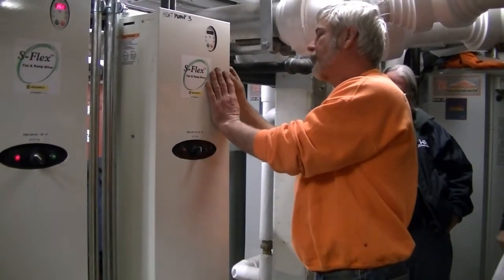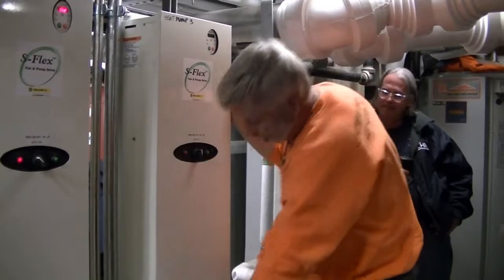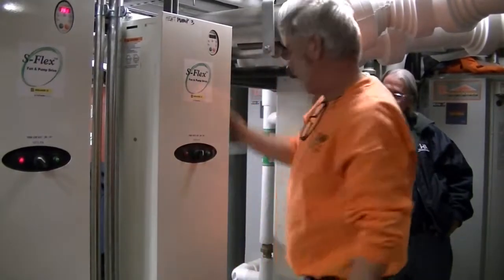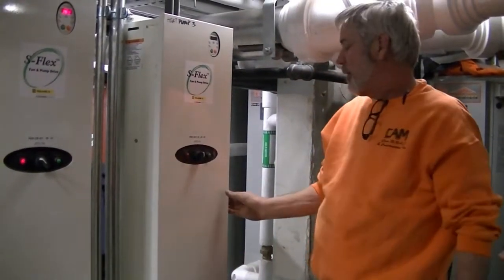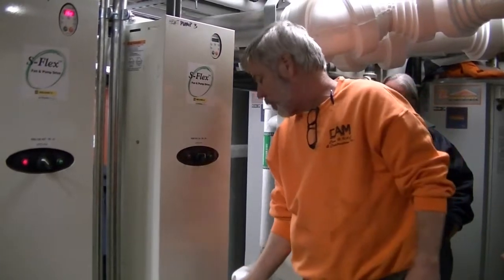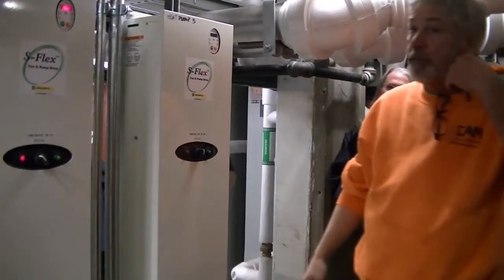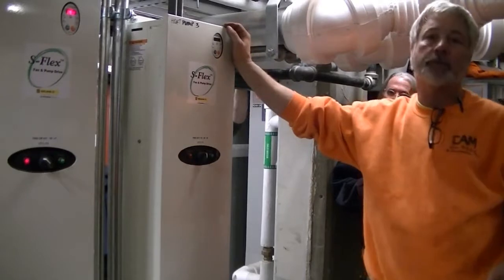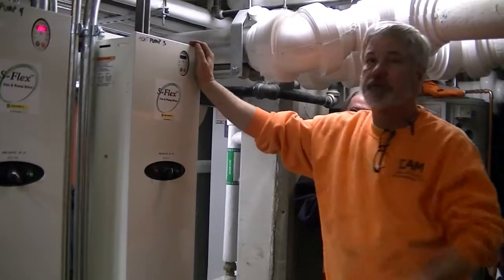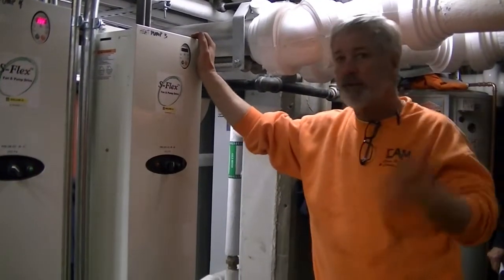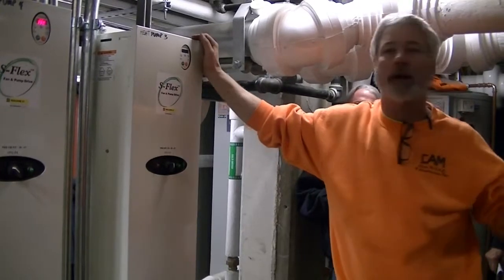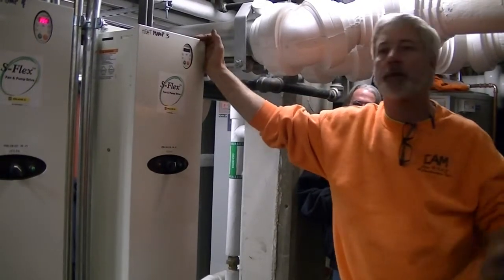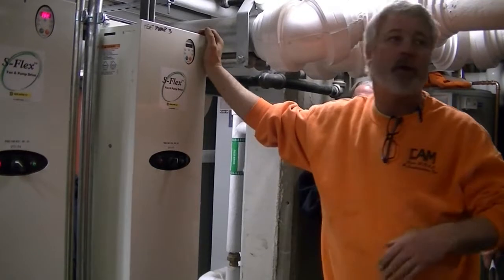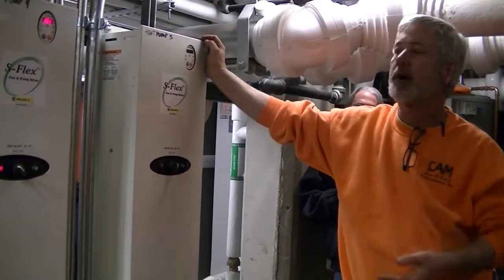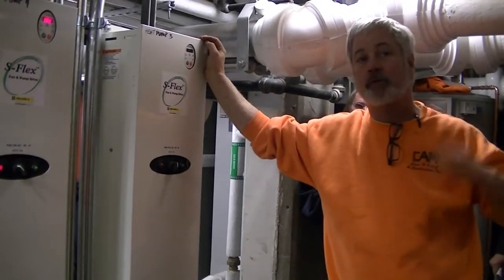What we do, and this is part of your control layout, is all the apartments have fan coils in them. All the fan coils have zone valves in them. The pumps are designed so that all the valves are open. The valves start getting satisfied and the heat satisfied in the apartments, the valves start closing down. You don't need the full capacity of the pump, so the pump starts to ramp down.